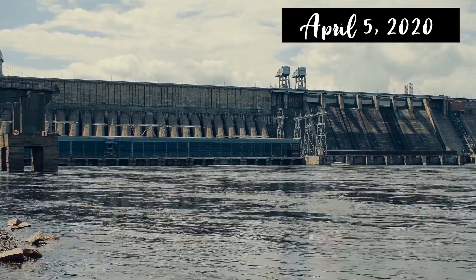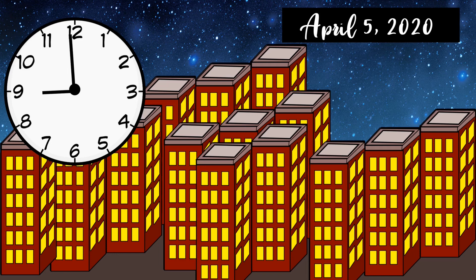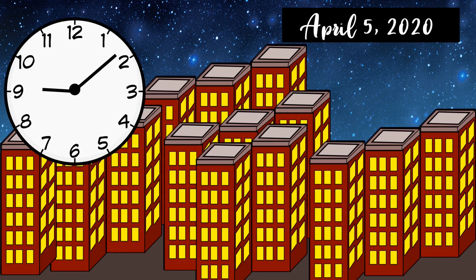Hydropower plants were ramped up to full capacity before the event to make up for the reduced generation from thermal power plants, and then dropped rapidly to less than 10% as people started switching their lights off. At the end of 9 minutes, they were ramped back up to cope with surging demand.